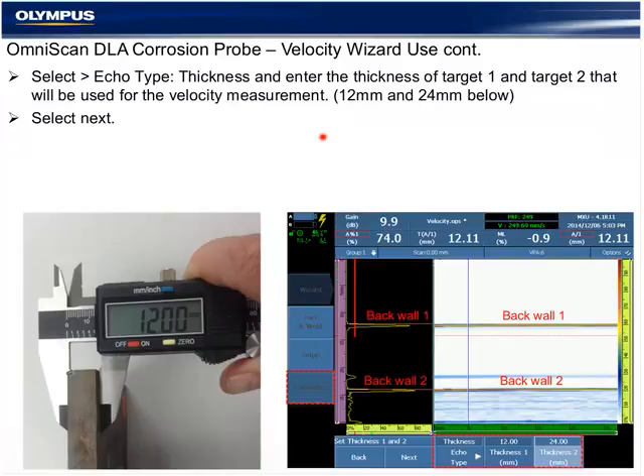So in cases where we do actually have to change the velocity, duplex, we're starting to see more exotic materials that are requiring inspection. Keep in mind that this probe is a 7.5 megahertz probe, so that's optimized for carbon steel. More attenuative austenitic materials might require a different frequency of probe. So if a velocity measurement using the wizard has to be made, it's made on one A-scan, and we do not use the nominal thickness of the pipe or plate. It could be out 10%, which would be normal. So we either want to use a reference standard made of the new material or use mechanical calipers to measure something prior to taking the reading so the velocity calculation will be correct.